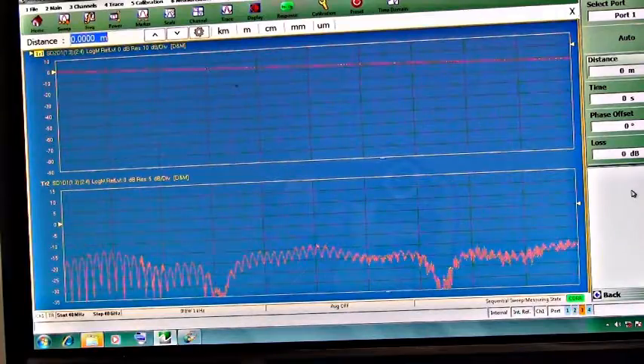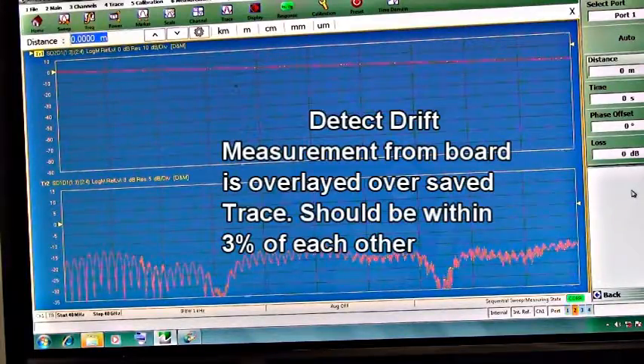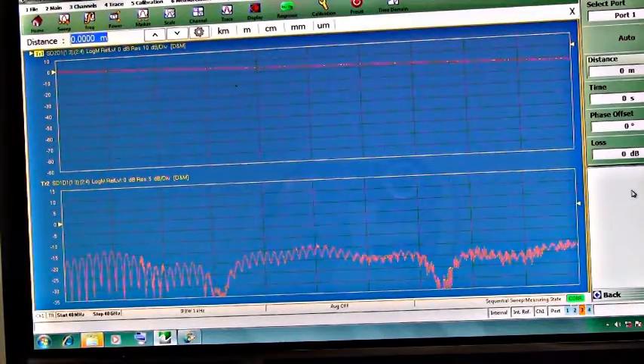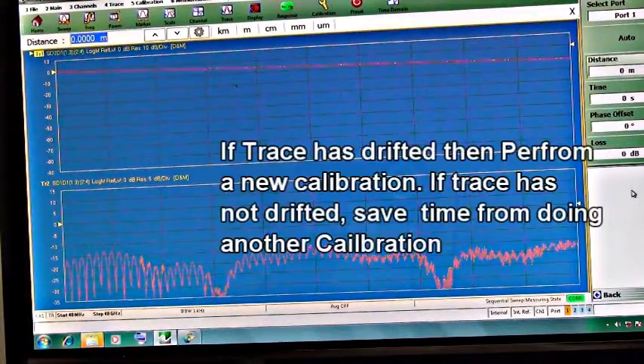So maybe your frequency plan is slightly different, then you can use a new set of files. But the good thing is you have a board that's standards, and you can compare the saved data versus the new calibration data. So if your system drifts for any reason, you can come back and actually measure the board and compare it to the data before to see if it's changed. If it has changed, then of course you need to do a new calibration. If it has not, you can assume your calibration is probably good.